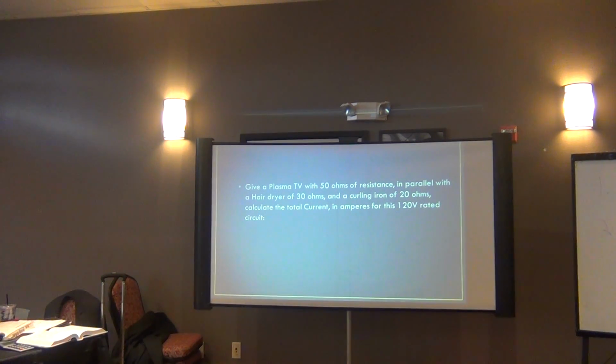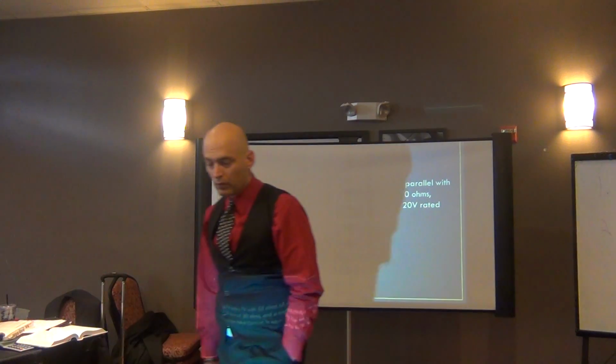It's in Article 200? Yeah, 200, straight up 200. So the gray, yeah, gray stripes. So 200.6 being sizes that are larger than 6 AWG. Your smaller ones are going to be under 200.6(A) and (B). Sorry, number 6 or smaller is A, and B is number 4 and larger. I got it backwards. Dot 4, B is 4 and larger, and then A is 6 and smaller.